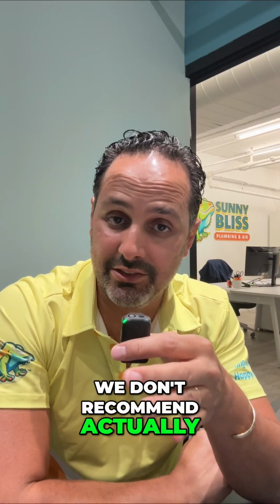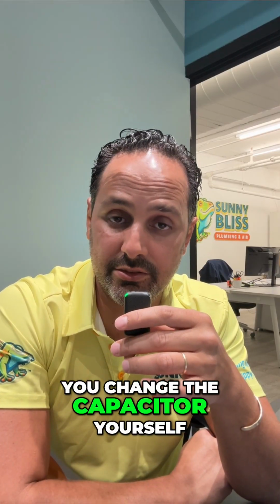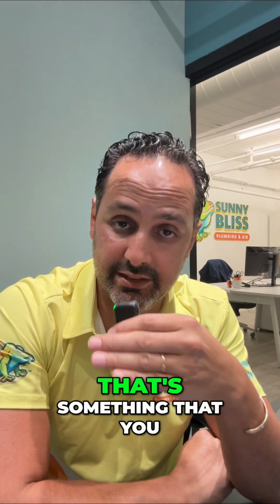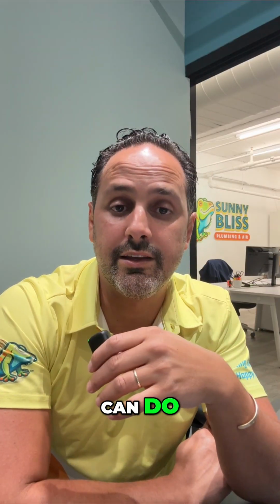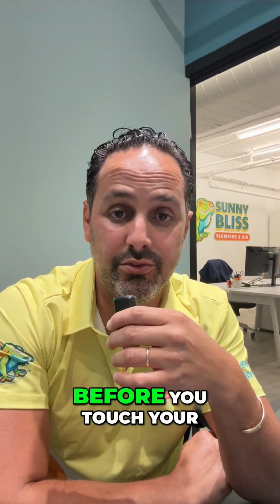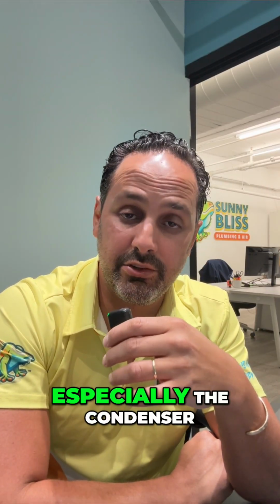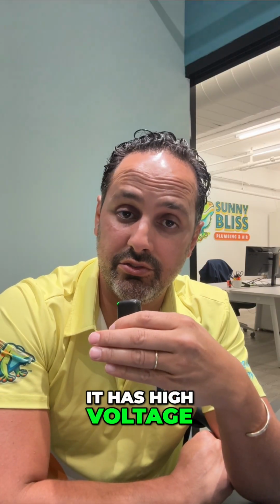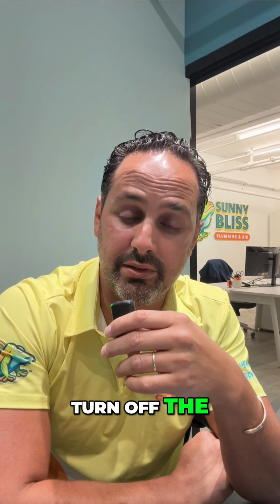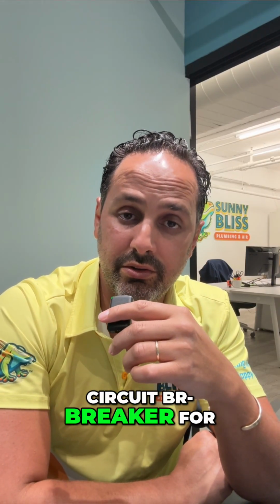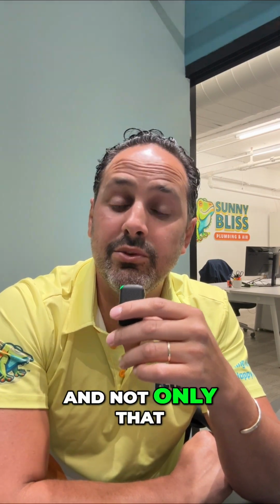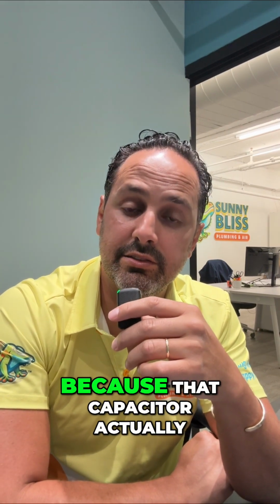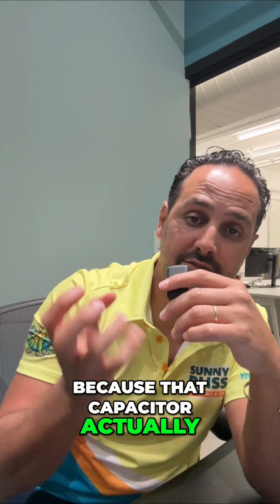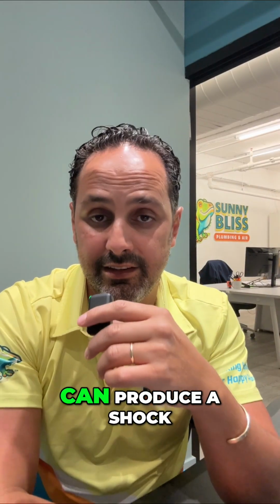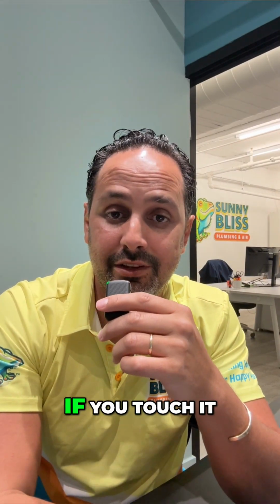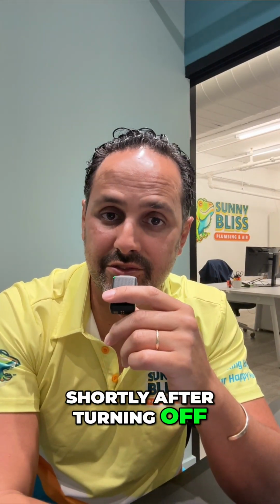We don't recommend you change the capacitor yourself, but if you're interested, yes, that's something you can do. Most importantly, before you touch your HVAC unit, especially the condenser, it has high voltage, so you need to turn off the power, the circuit breaker for the HVAC unit. And not only that, you have to wait, because that capacitor stores energy and can produce a shock if you touch it shortly after turning off the power.